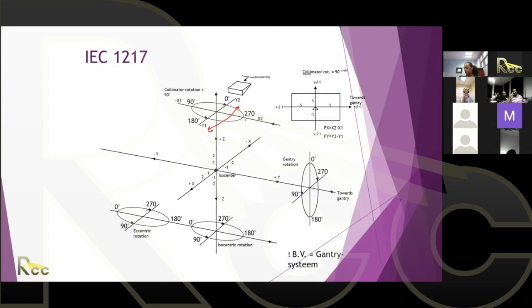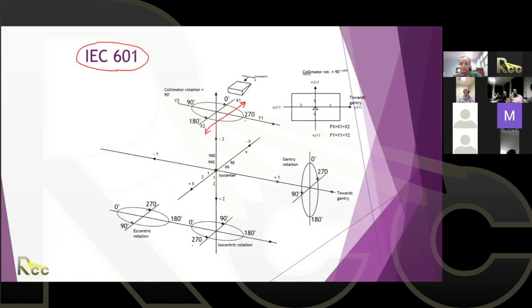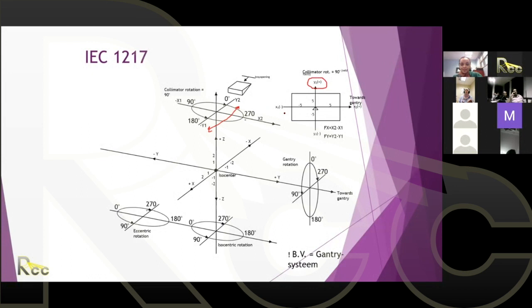The direction itself hasn't changed - the wedge is in exactly the same direction, but the naming changed. So you have to be careful, because X2 became Y1 and X1 became Y2, or the reverse. This is one of the important points. Now pay attention, for example: look at this. In 601, I have X1 in this direction, and let's say Y2 in this direction. In 1217, X1 becomes Y2, and Y2 becomes X1.